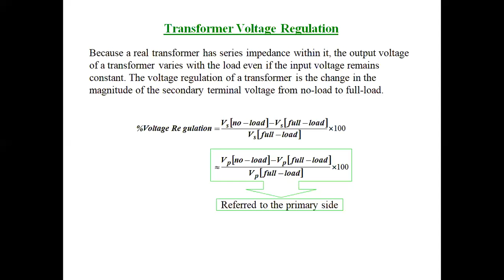The next term is regulation. If the load is applied, the secondary voltage goes down, that is, there is some voltage drop. The voltage regulation is nothing but no load voltage minus load voltage, divided by load voltage. In this way, we can find how much voltage is dropped. If our regulation value is very high, the transformer is not in good condition. If the regulation value becomes low, that means our transformer is in good condition, because the drop is very low.